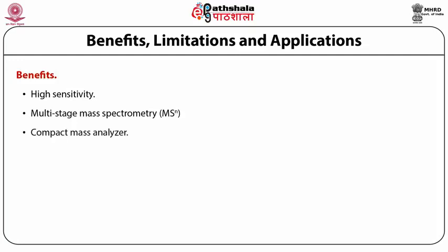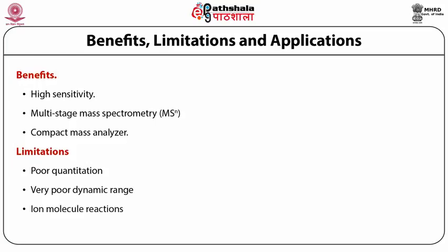It, however, has some limitations which are listed here. It has poor quantification, so if you want to do quantitation, maybe you have to go to other mass analyzers. It has very poor dynamic range. A lot of ion molecule reactions take place because the ions reside there for a longer time. The collision energy is not well defined in CID MS mode.